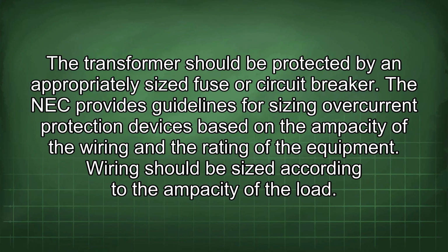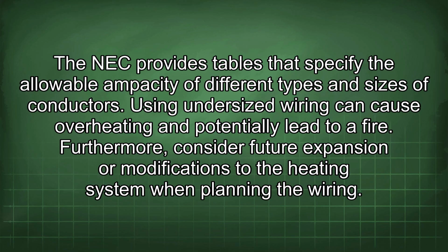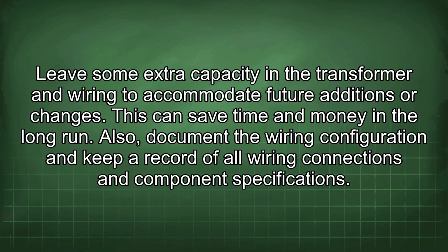The NEC provides guidelines for sizing overcurrent protection devices based on the ampacity of the wiring and the rating of the equipment. Wiring should be sized according to the ampacity of the load. The NEC provides tables that specify the allowable ampacity of different types and sizes of conductors. Using undersized wiring can cause overheating and potentially lead to a fire. Furthermore, consider future expansion or modifications to the heating system when planning the wiring. Leave some extra capacity in the transformer and wiring to accommodate future additions or changes. This can save time and money in the long run.